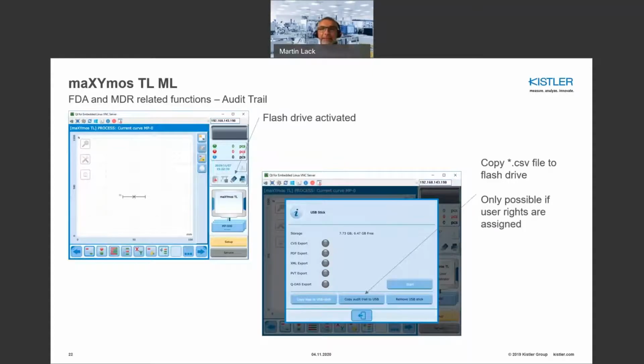We also implemented in the maXYmos TL ML the possibility to take the audit trail out of the device via a USB stick. But not only via USB stick - you can also transfer the audit trail information via the field bus and send it to a server. So you activate the audit trail via the field bus and send the information to the connected server.